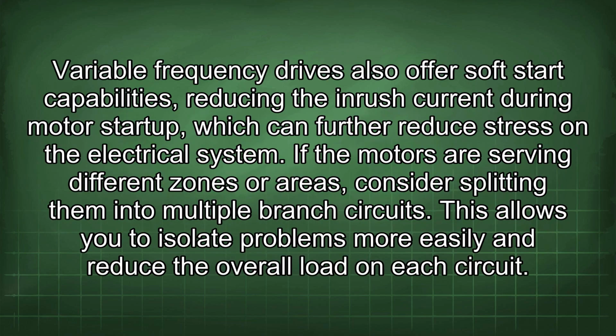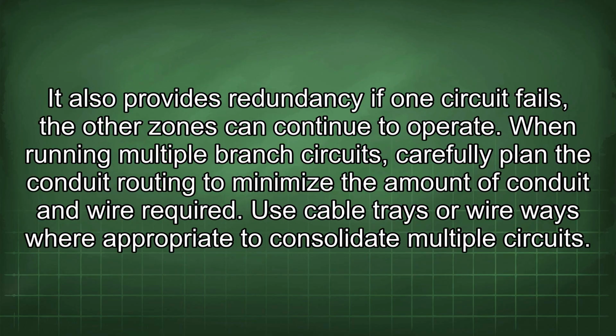Variable frequency drives also offer soft start capabilities, reducing the inrush current during motor startup, which can further reduce stress on the electrical system. If the motors are serving different zones or areas, consider splitting them into multiple branch circuits. This allows you to isolate problems more easily and reduce the overall load on each circuit. It also provides redundancy. If one circuit fails, the other zones can continue to operate. When running multiple branch circuits, carefully plan the conduit routing to minimize the amount of conduit and wire required. Use cable trays or wireways where appropriate to consolidate multiple circuits.